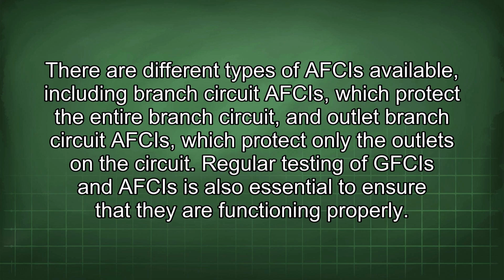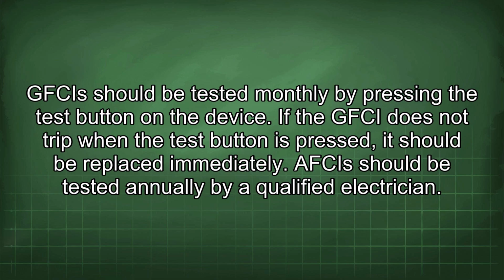Regular testing of GFCIs and AFCIs is also essential to ensure that they are functioning properly. A GFCI should be tested monthly by pressing the test button on the device. If the GFCI does not trip when the test button is pressed, it should be replaced immediately. AFCIs should be tested annually by a qualified electrician.